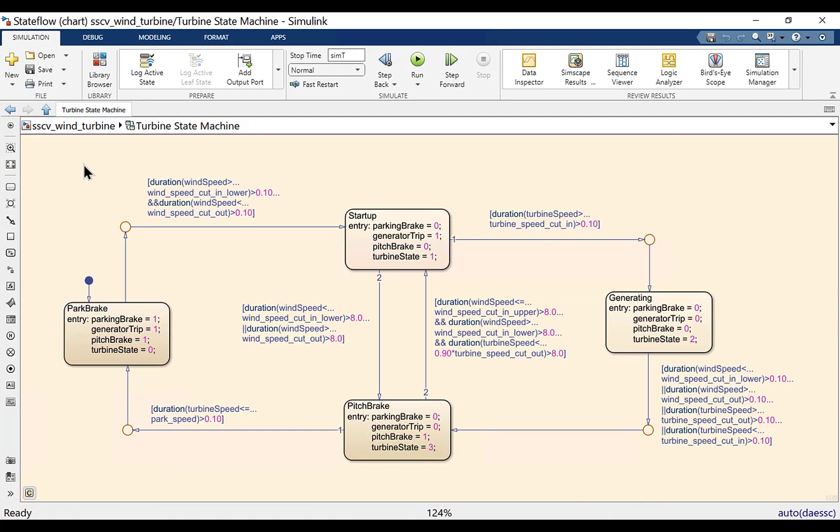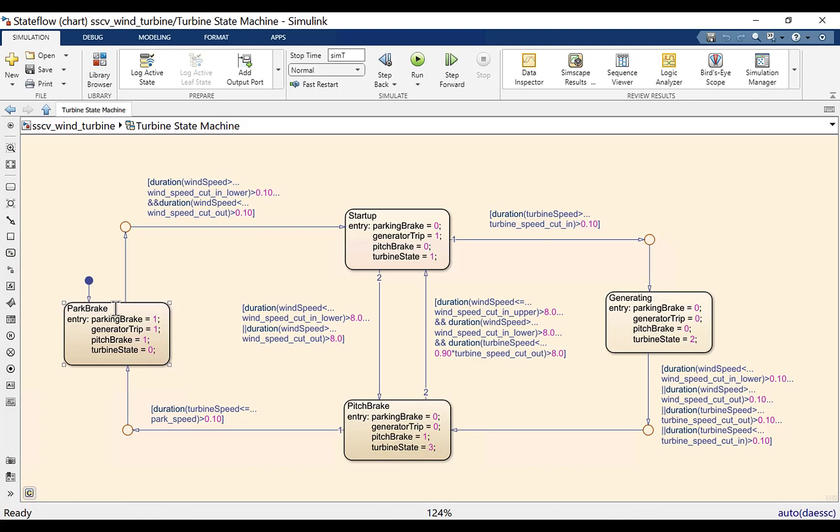The supervisory control of the wind turbine defines the mode of operation of the wind turbine. The mode transition takes place based on the wind speed and the rotor rotation speed. In the park brake mode, turbine hydraulic brakes are applied to the rotor hub. Once the conditions become suitable, the hydraulic brakes are released and turbine enters the startup mode.